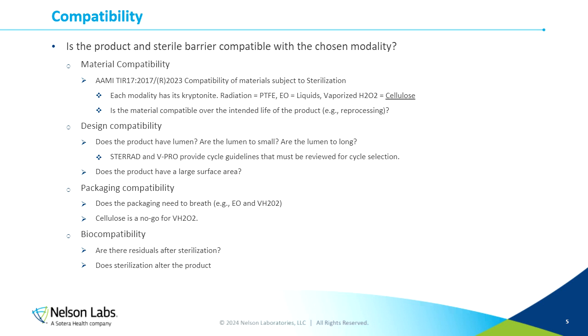One of those first tools is AAMI TIR17. It was initially published in 2017 and has recently been reaffirmed, and it has information on compatibility of materials subject to sterilization. This is a very beneficial TIR, as it provides information for vaporized hydrogen peroxide, but also other sterilization modalities as well. The reality is, each modality has its advantages and disadvantages, and part of that is each modality has its kryptonite. Steam sterilization, or if you prefer, moist heat sterilization, is a high temperature process and can be damaging to certain materials. Likewise, other sterilization modalities have compatibility concerns as well.